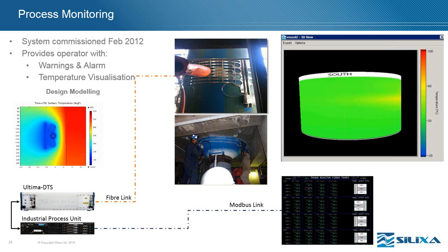Now, we continuously monitor the temperature information, and what you can see here on the top right-hand corner is actually the formation of a hotspot that was created along the vessel. This was done during the factory acceptance test, and the system will detect these hotspots and send alarms through Modbus links to a SCADA network, or allow the operator to visualize in real time the temperature distribution of the surface skin.